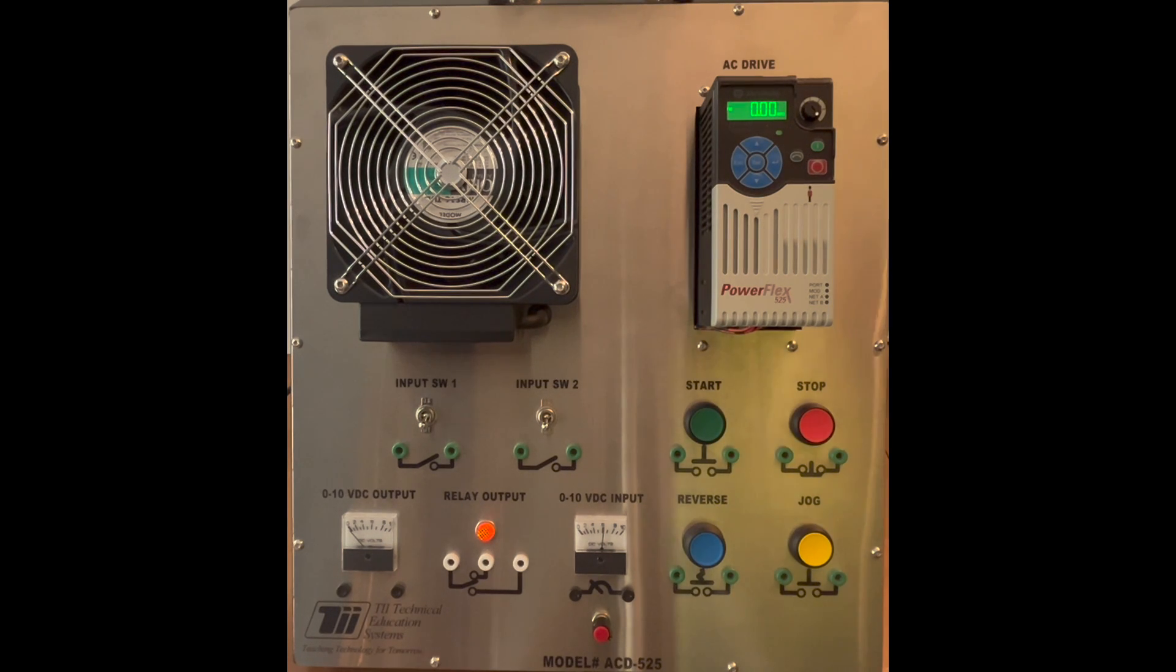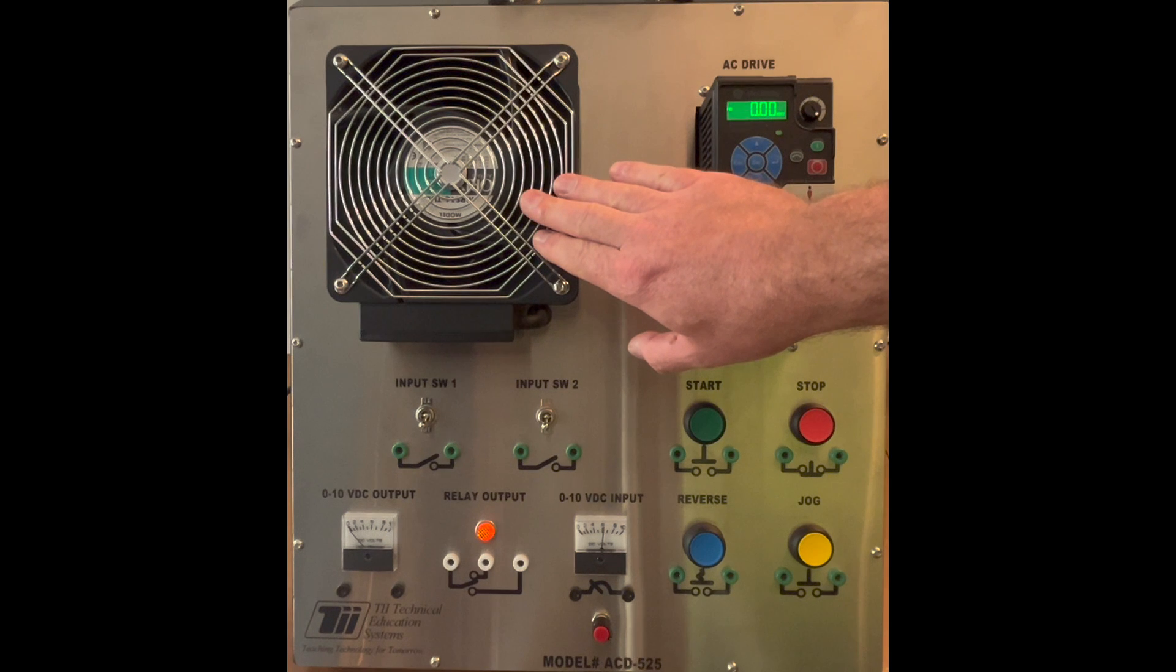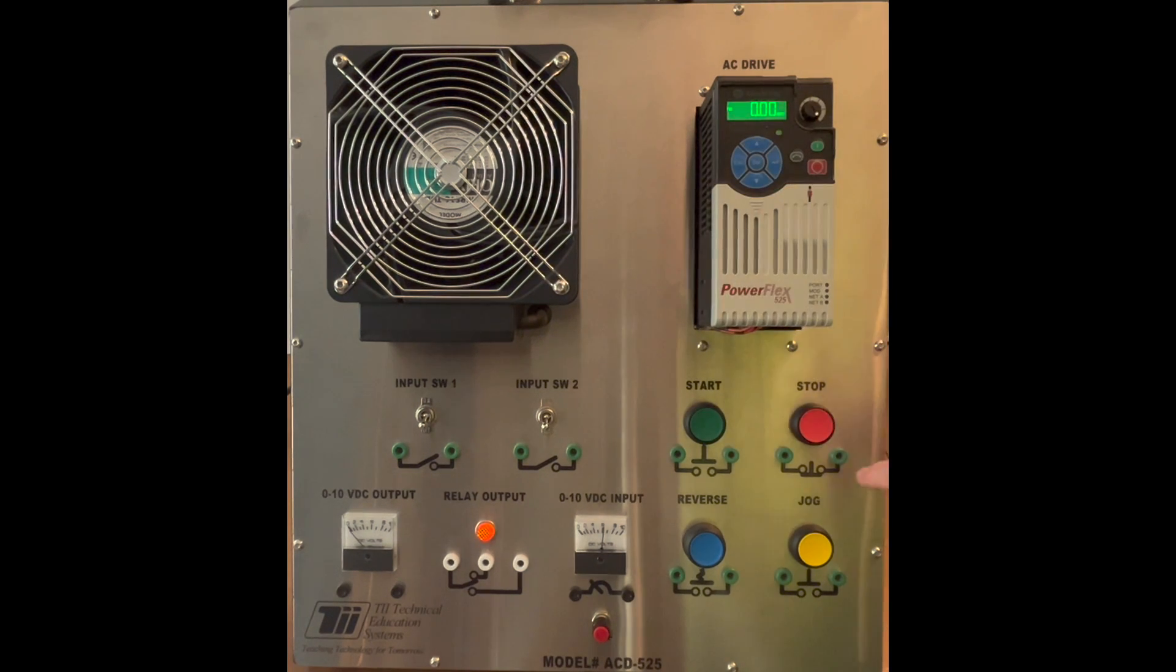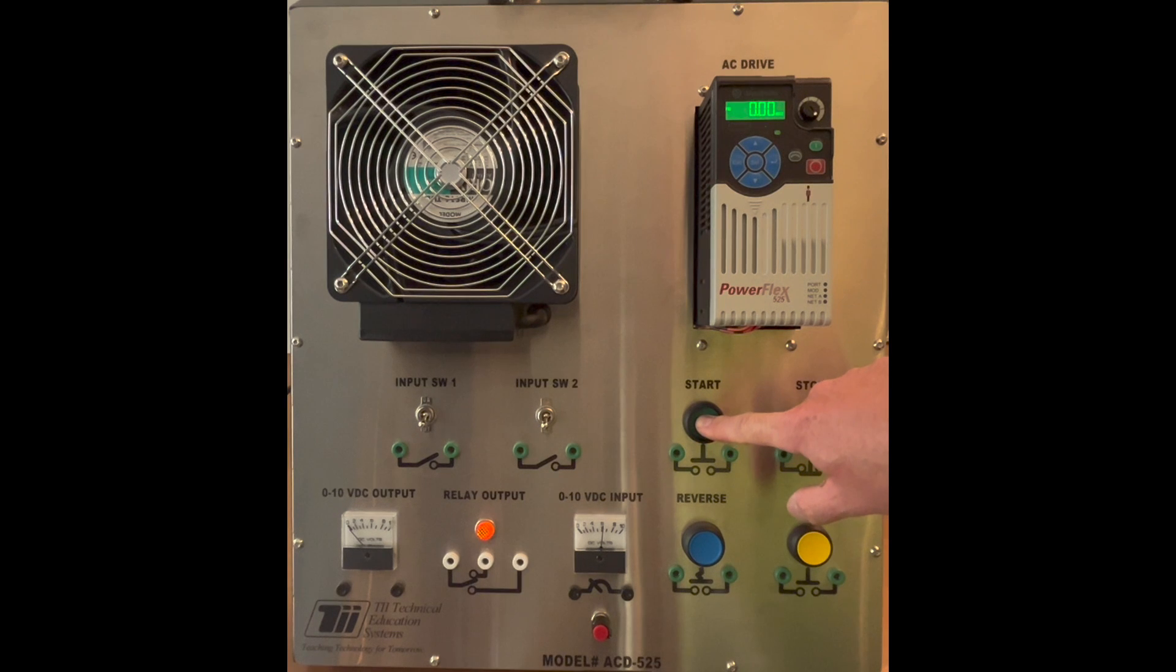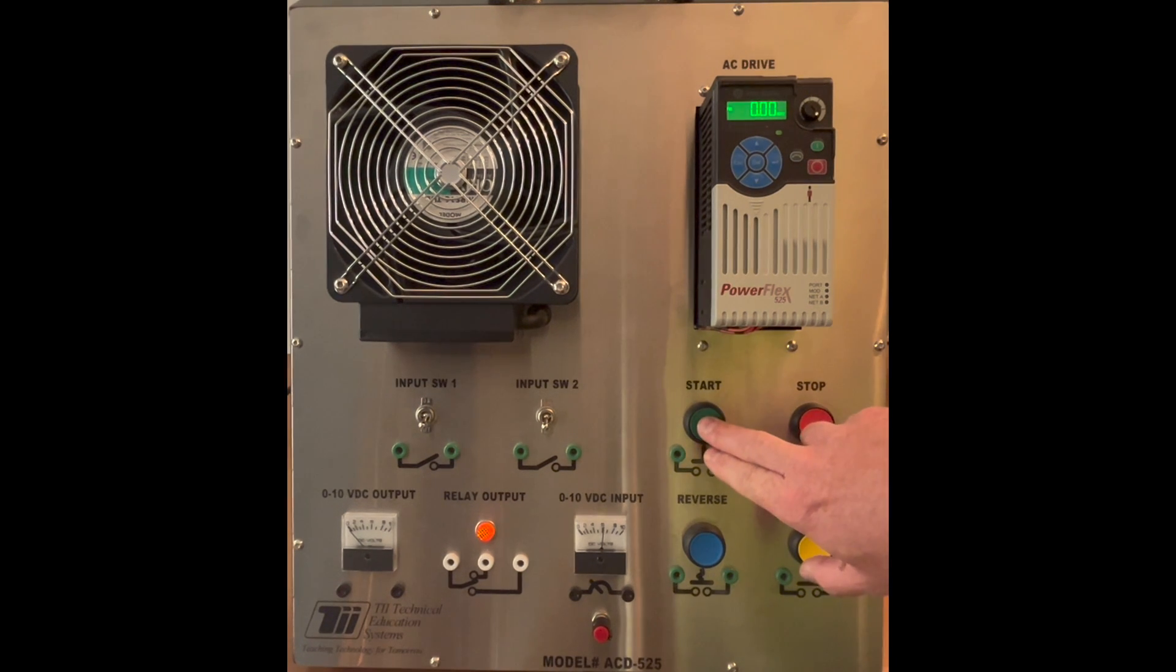What three-wire control is, is we want to be able to use the start button to start the VFD running at whatever frequency it is set at, and then let the button go. If I activate the stop button, I want it to stop. Two-wire control is when I just have my start button activated, and then I have to hold it to let the motor run. But in this case, we want to be able to activate it, walk away, then hit the stop button to turn it off.